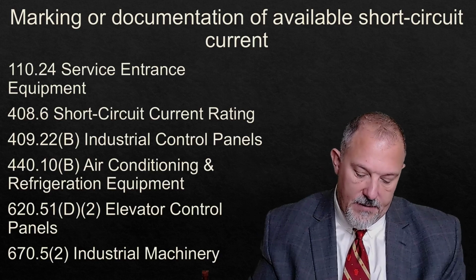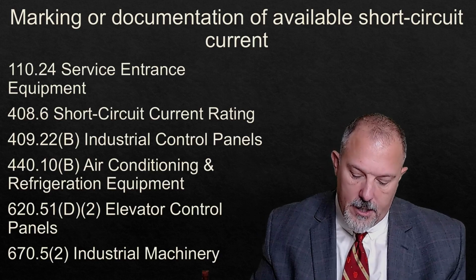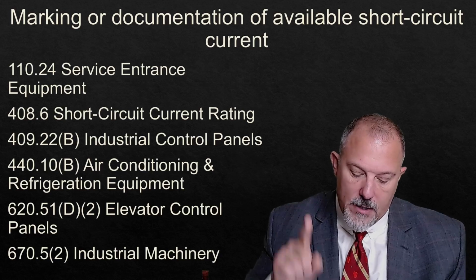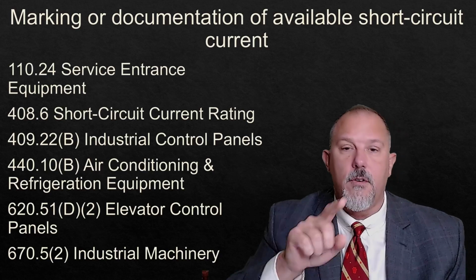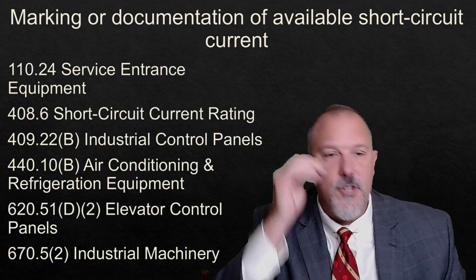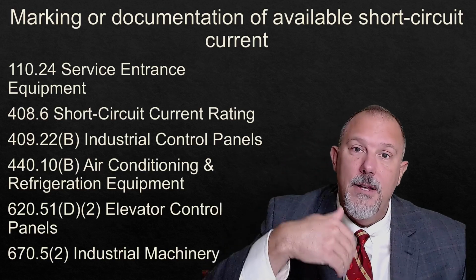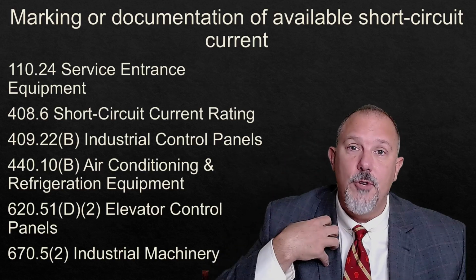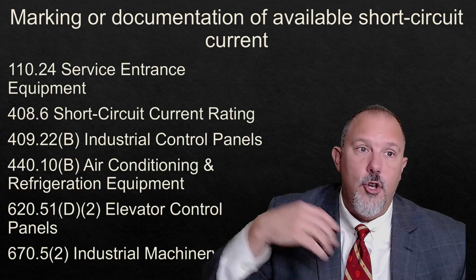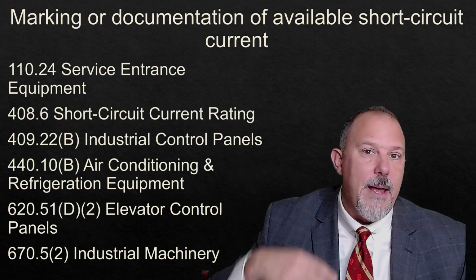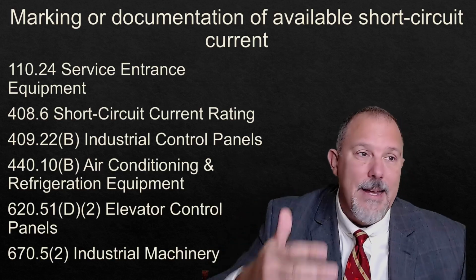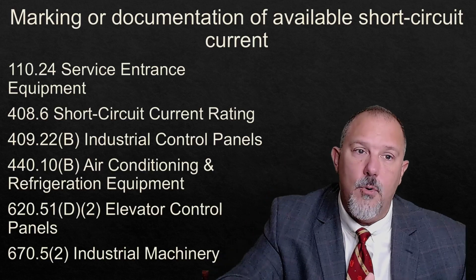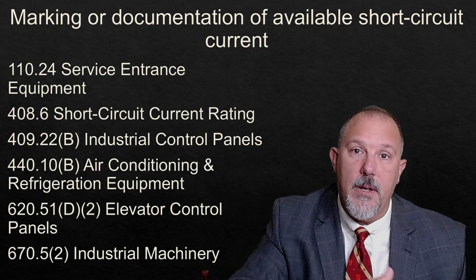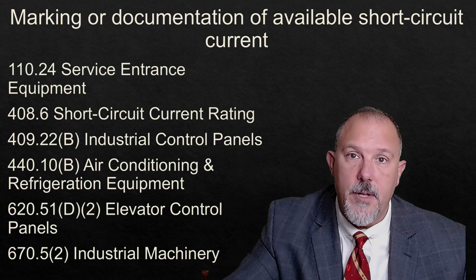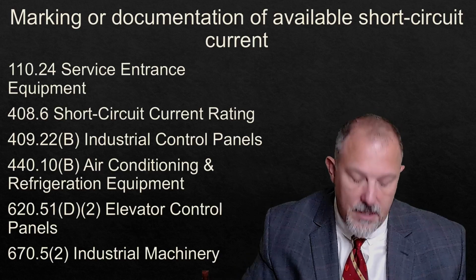110.24, available fault current. Service equipment in other than dwelling units shall be legibly marked in the field with the available fault current. Why in the field? Fault current is dependent upon a lot of different parameters that nobody knows, no manufacturer knows, when that product ships. The manufacturer cannot label available fault current on equipment because they don't know where it's going to be installed. So it says in the field.